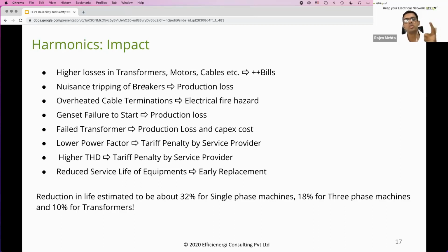It is a tripping of breakers because of higher RMS harmonic current, or a generator not being able to start because of a huge amount of harmonic rich load in the system, or a lower power factor, because harmonics can pull your power factor down. It can also be because of a higher harmonic penalty which the service providers have started levying, like in Tamil Nadu, in Maharashtra, and other states. Or it can be reduced service life of equipment like cables and bus ducts, which get overheated over a period of time, and hence their life reduces.